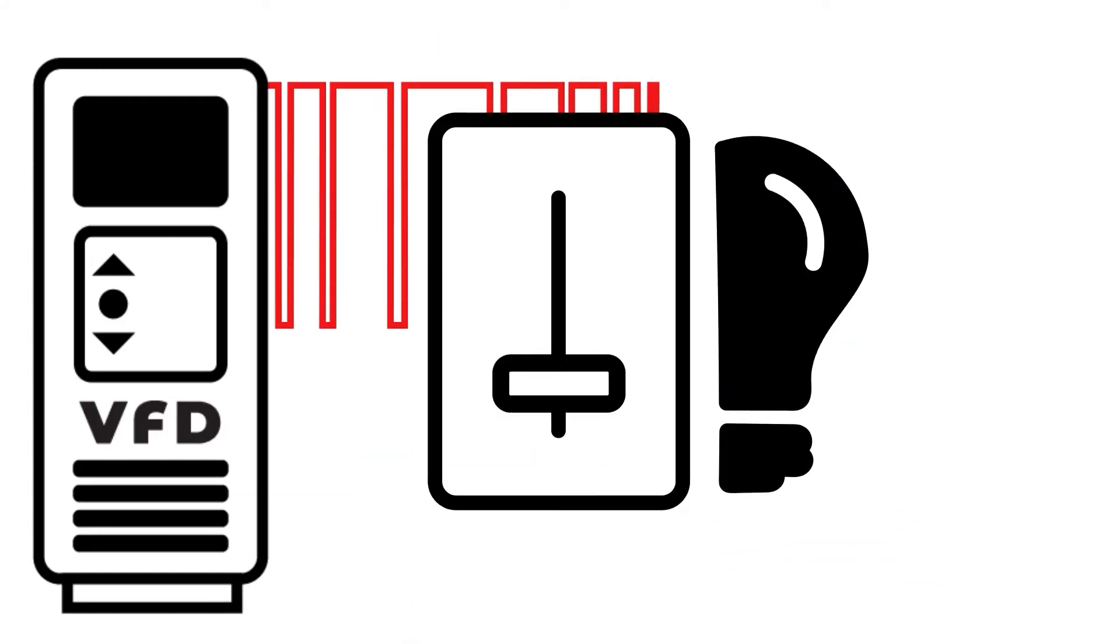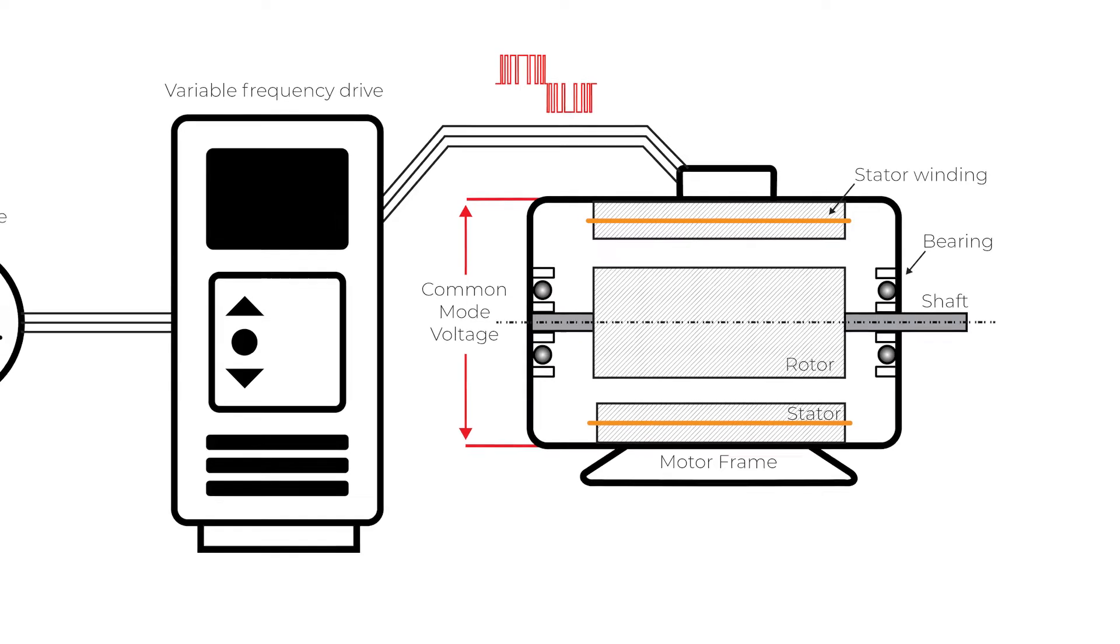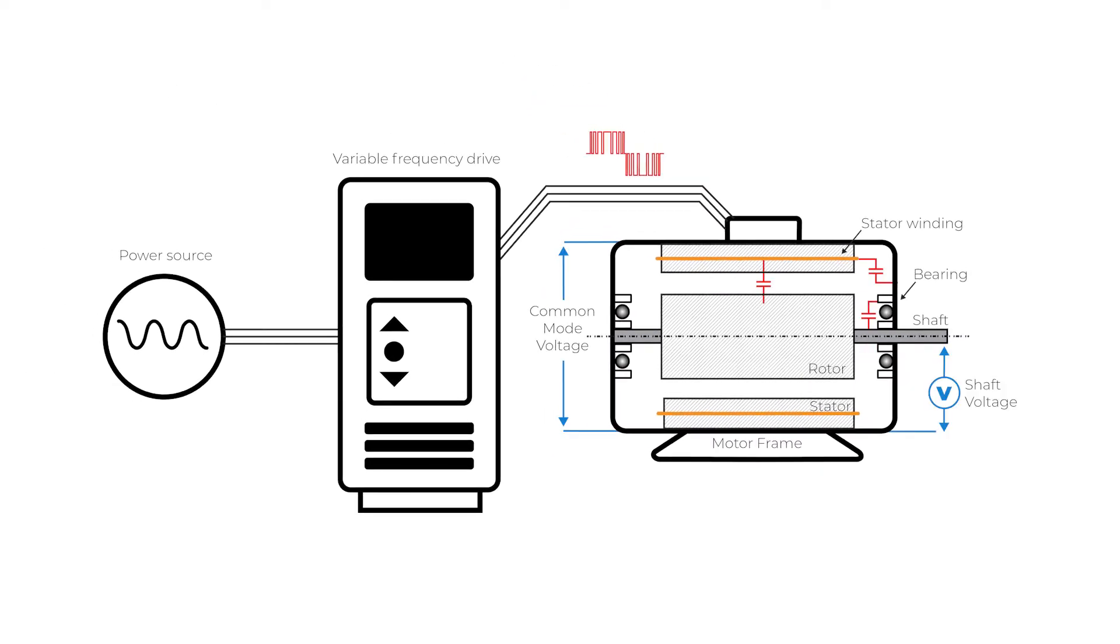Fast switching of the IGBT creates parasitic capacitances in the motor. Common mode voltage and capacitances are sources of a shaft voltage.